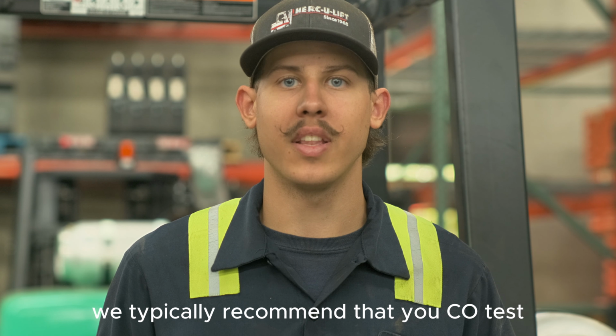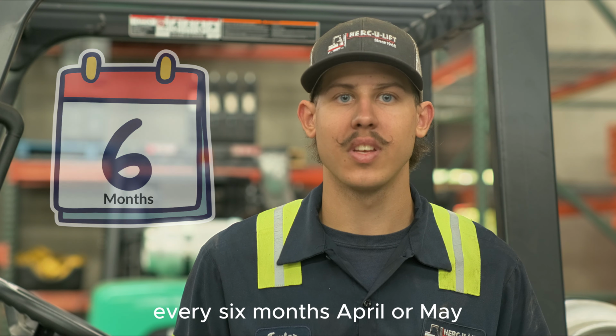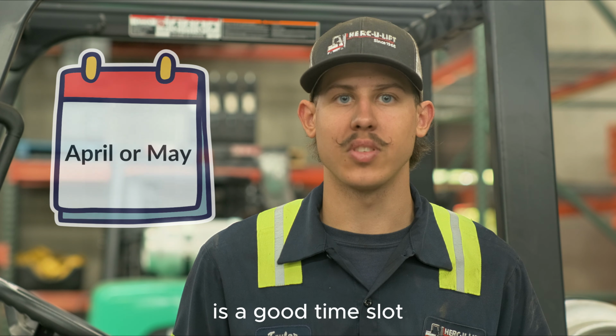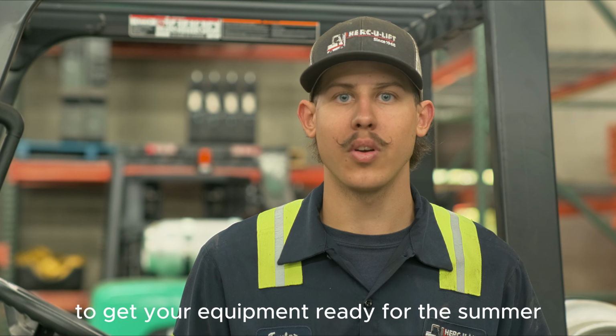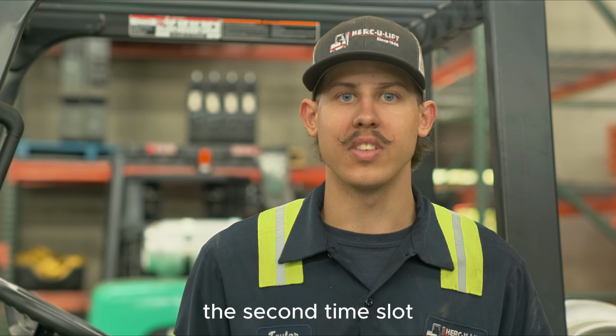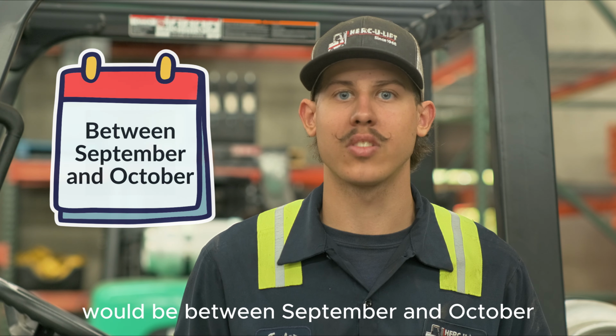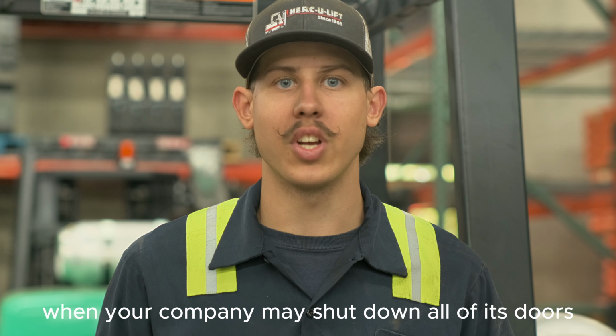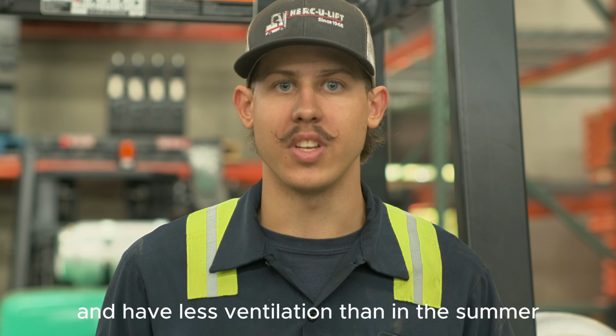We typically recommend that you CO test every 6 months. April or May is a good time slot to get your equipment ready for the summer during your busiest times. The second time slot would be between September and October, when your company may shut down all of its doors and have less ventilation than in the summer.